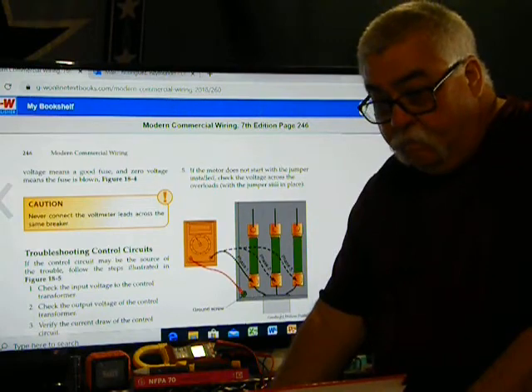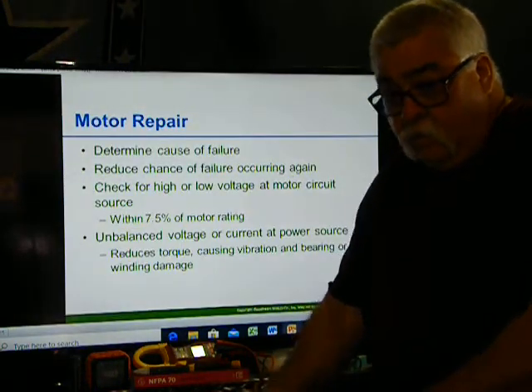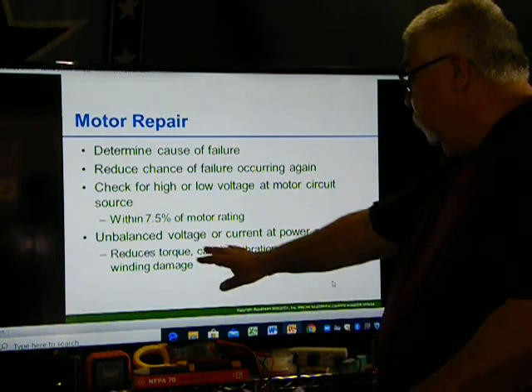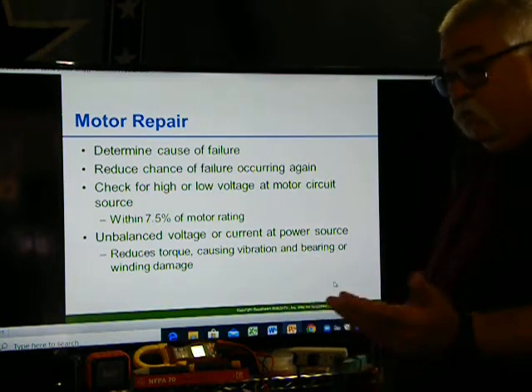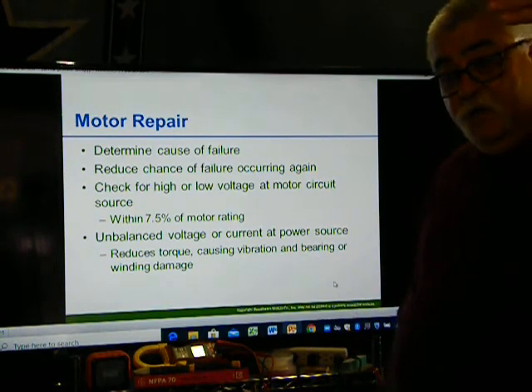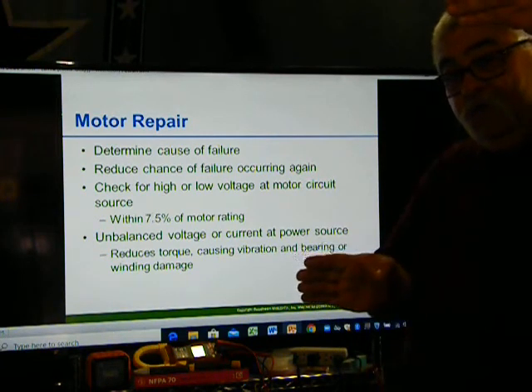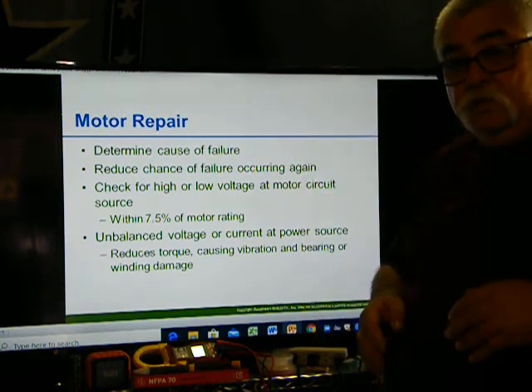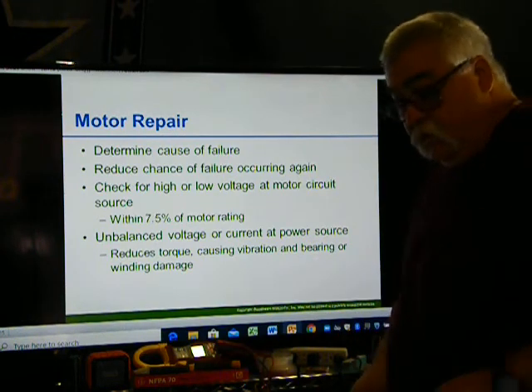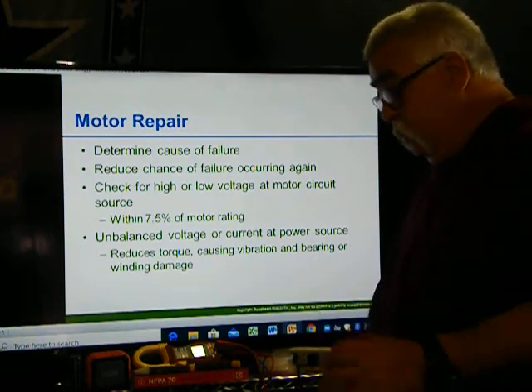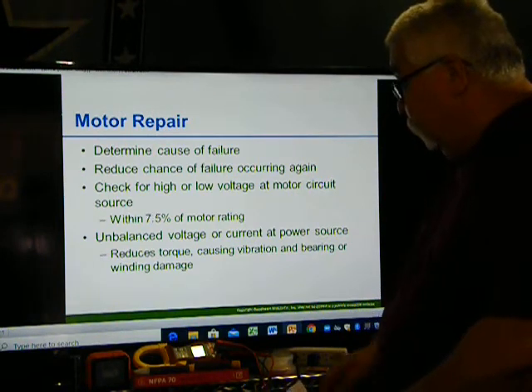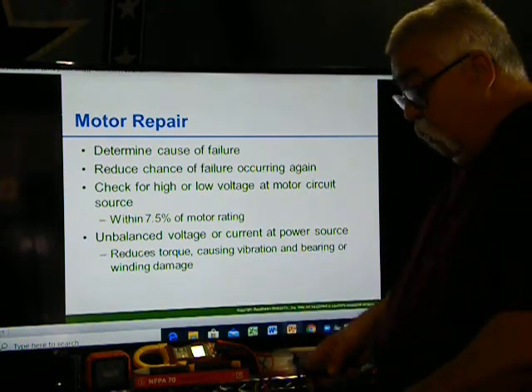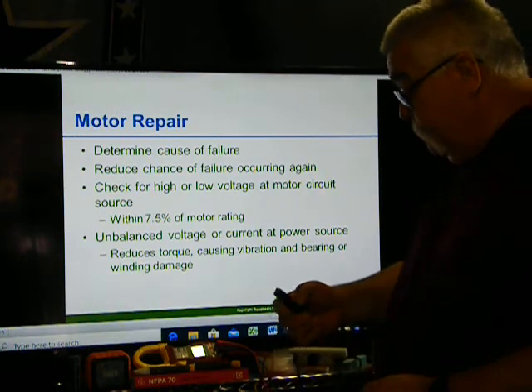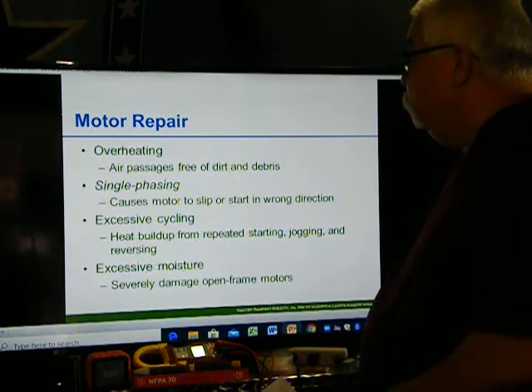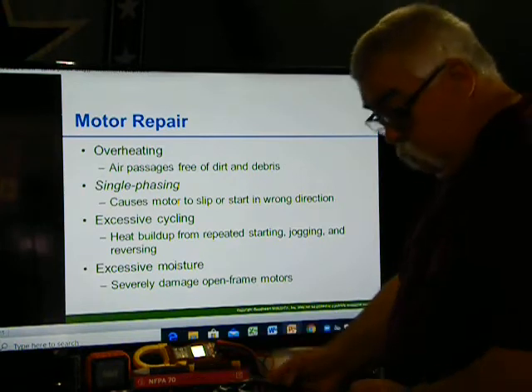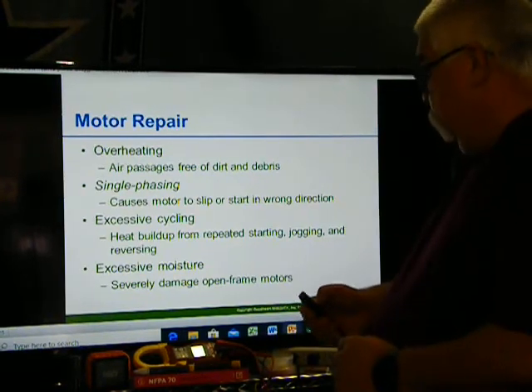Go back to the PowerPoint. So, unbalanced voltage and current at the power source, guess what? Current changes. Because if I got 118 volts here and I got 105 volts here, well, the current changes. Excessive current can cause extra heat and damage the windings. Overheating.